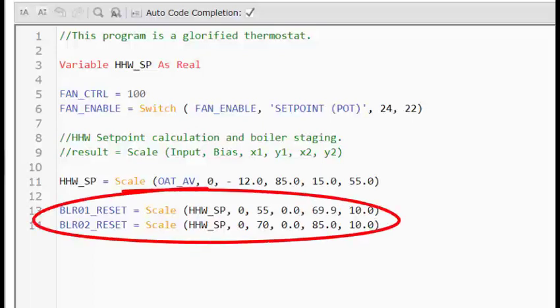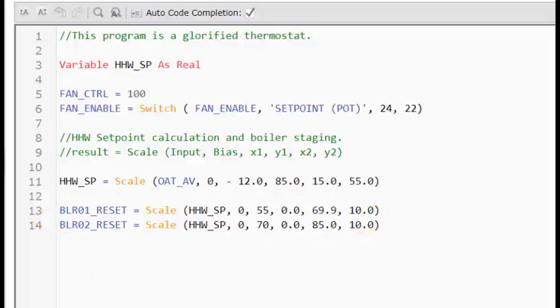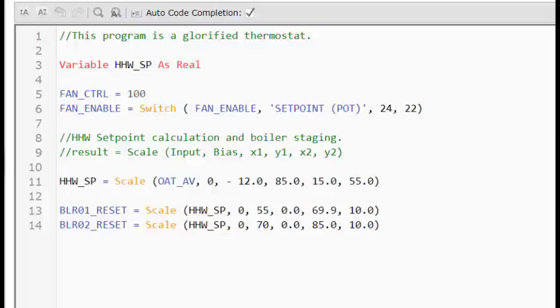Here I have programmed two more lines of code using the scale statement. Instead of looking at the outdoor air sensor, these look at the calculated heating hot water temperature set point. And then split the calculations. Starting at 55 degrees, boiler number one starts to receive a 0 to 10 volt reset signal.